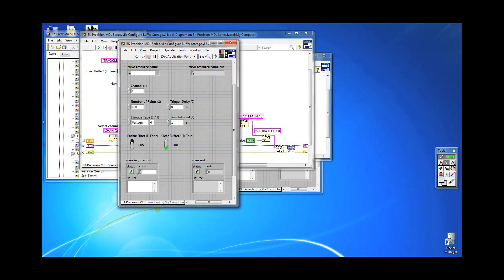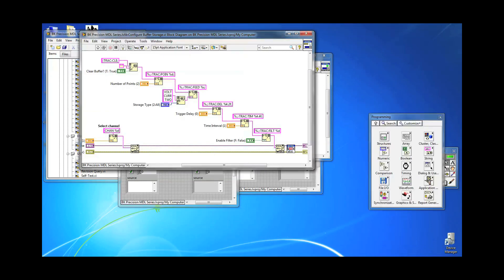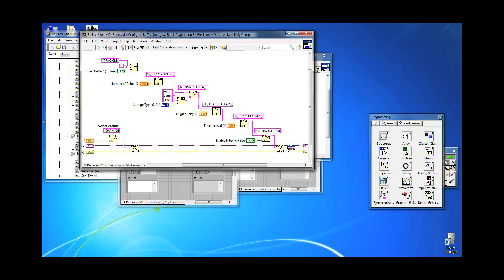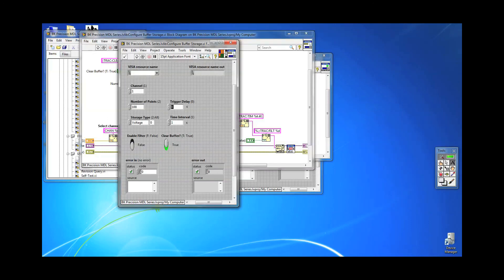Buffer storage operation begins after receiving a trigger. If you want to add a delay after the trigger before the operation begins, send the trace delay command TRAC:DEL. You can delay up to 3600 seconds. We will set it to 5 seconds by sending TRAC:DEL 5.